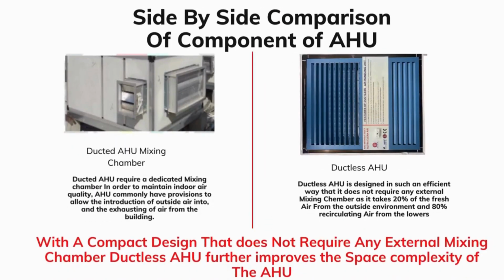A ducted air handling unit requires a dedicated mixing chamber in order to maintain the indoor air quality. Air handling units commonly have provisions to allow the introduction of outside air into the operation theatre, which exhausts all the air from the building. Whereas the ductless AHU is designed in such an efficient way that it does not require any external mixing chamber, as it takes 20% of the fresh air from the outside environment and the rest 80% by recirculating air from the lowers.